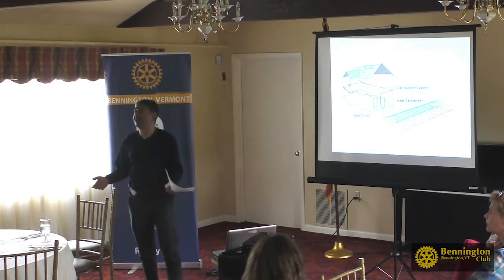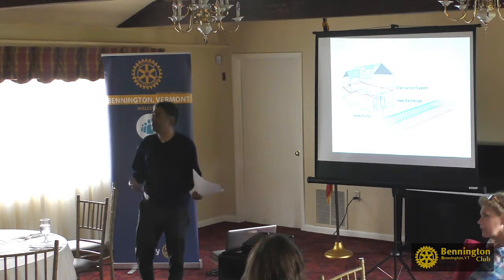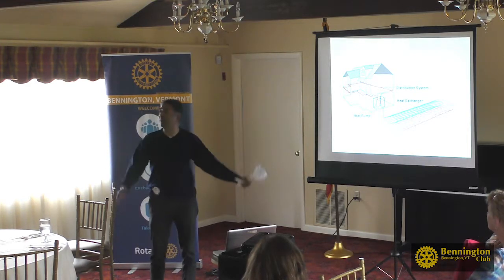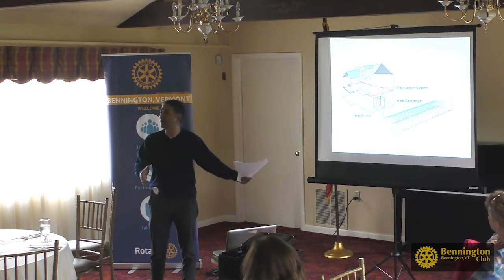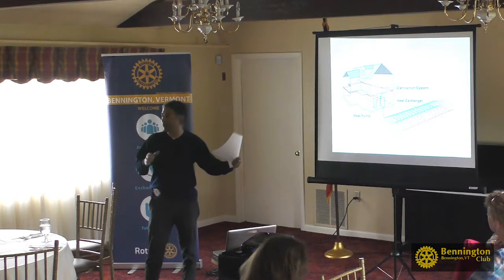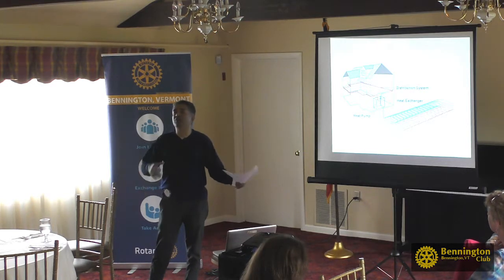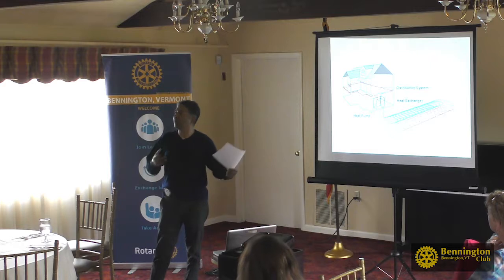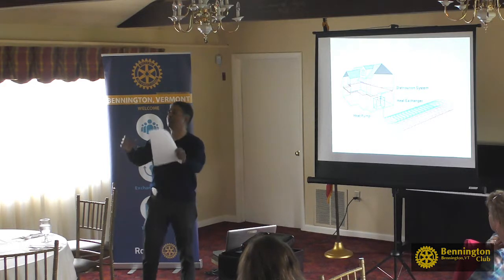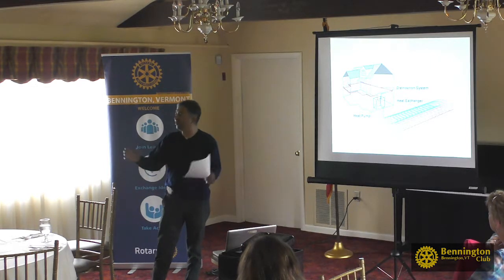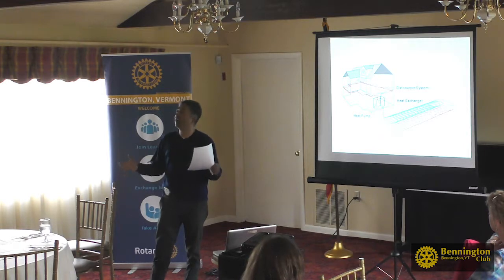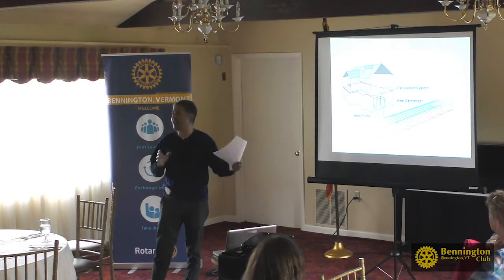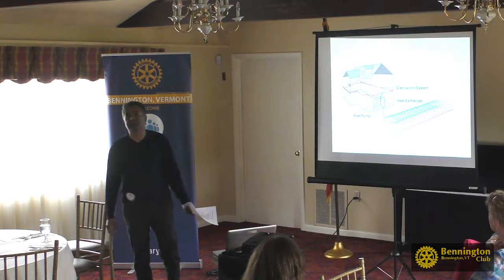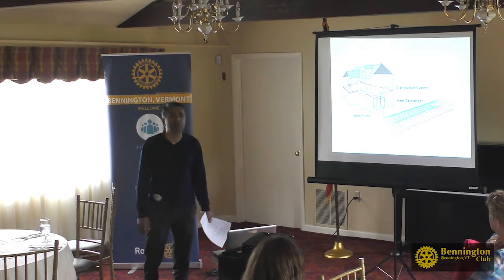So you have forced air ducts. You can have a big heat pump there, which displaces your forced air propane unit or forced air oil unit. You'll have to change the ducts though, because you need to have a certain velocity of the air to carry the air into all these rooms, and they may not be sized to the same capacities as conventional furnaces are. So you may have to change the ducts in those.